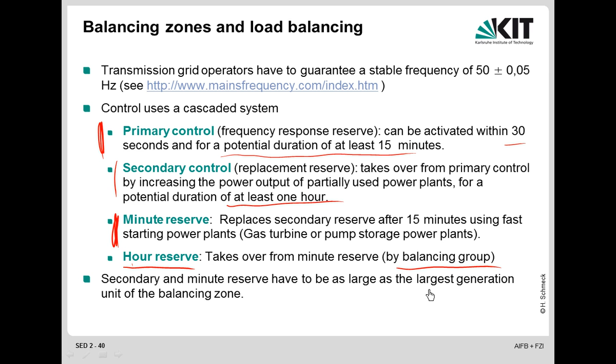And secondary and minute reserve have to be as large as the largest generation unit of the balancing zone. Why do we have that? This is the n-1 property, which means that even if one of the n elements that I have, which are providing stability for my system, fails, the remaining n-1 should still be able to provide stability. So if one of those systems fails, it has to be possible to replace that by other systems, that they just increase the power generation slightly, and then they can compensate the loss from the failure of one of those devices.